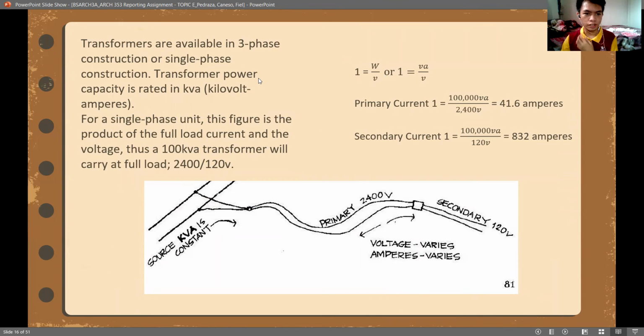Transformers are available in three-phase construction or single-phase construction. Transformer power capacity is rated in kilovolt amperes. For a single-phase unit, this figure is the product of the full load current and the voltage. Thus, a 100 kilovolt ampere transformer will carry full load at 2400 over 120 volts. So here is the solution. You're going to solve for the volt-amperes over the volts. So here, 100,000 volt-amperes divided by the 2400 volts. And here is the equivalent.